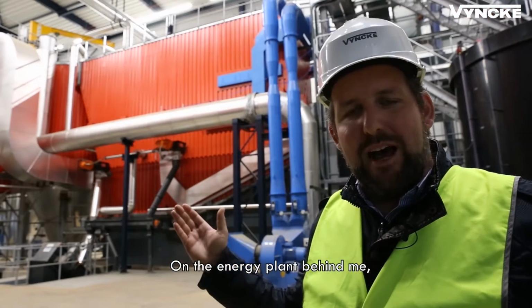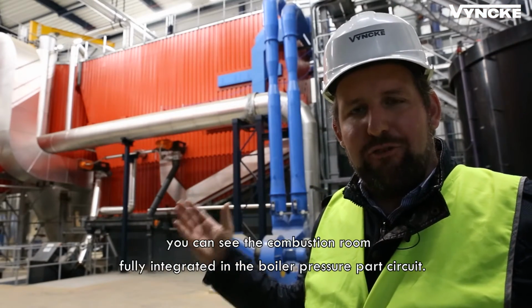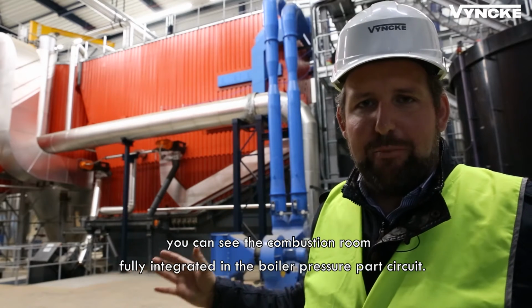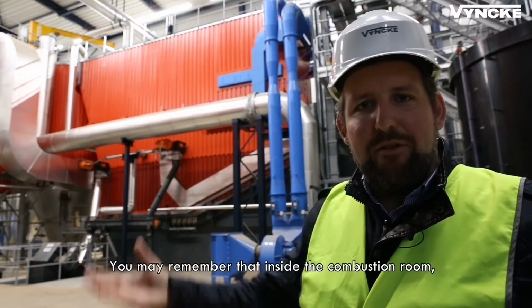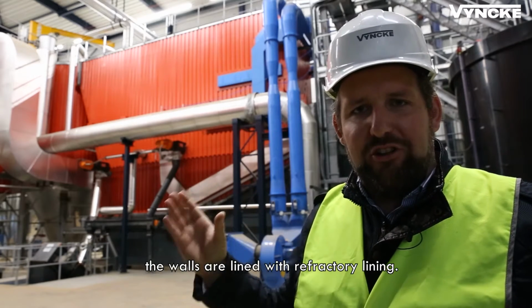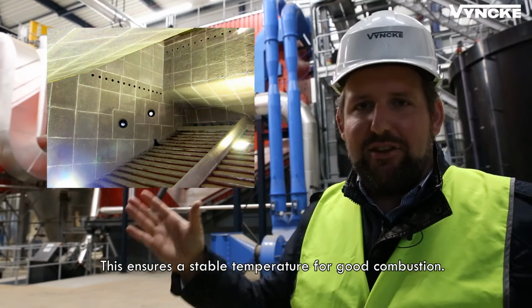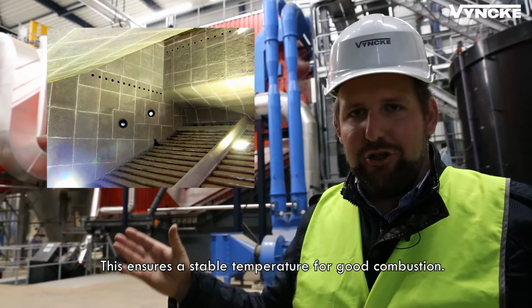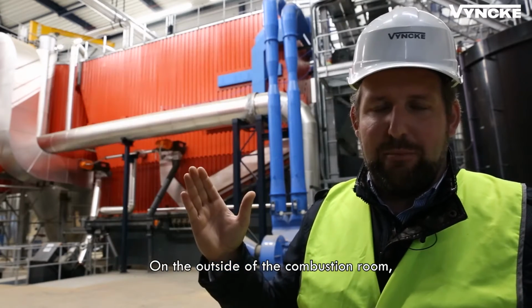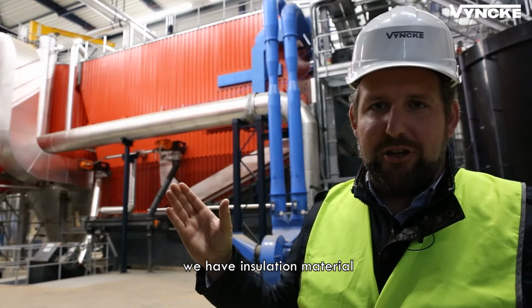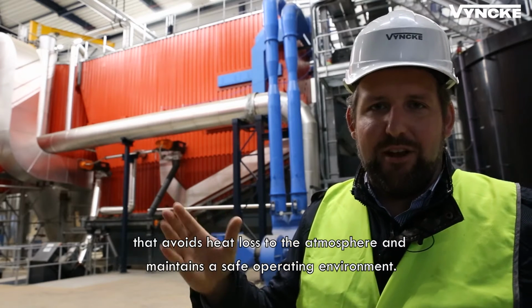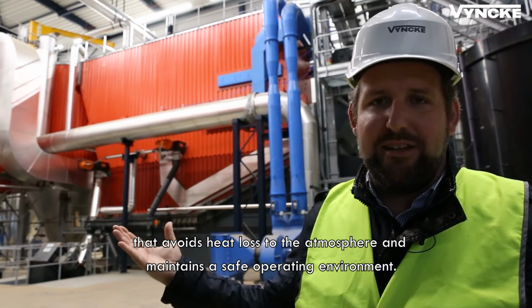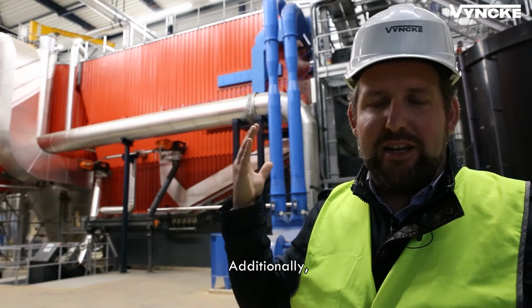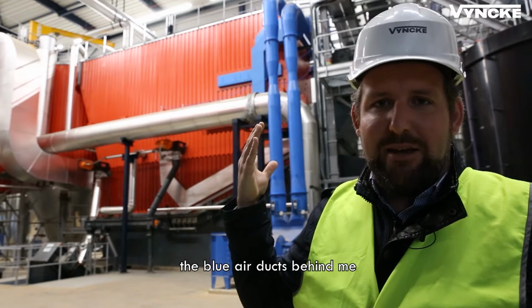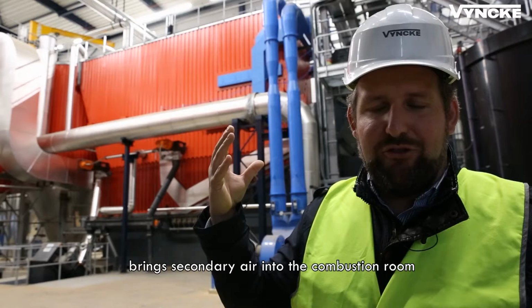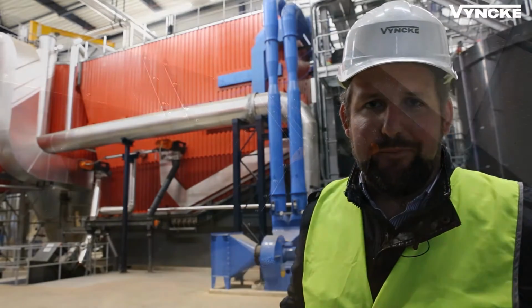On the energy plant behind me, you can see the combustion room fully integrated in the boiler pressure part circuit. You may remember that inside the combustion room, the walls are lined with refractory lining. This ensures a stable temperature for good combustion. On the outside of the combustion room, we have insulation material that avoids heat loss to the atmosphere and maintains a safe operating environment. Additionally, the blue air ducts behind me bring secondary air into the combustion room in order to complete the combustion.